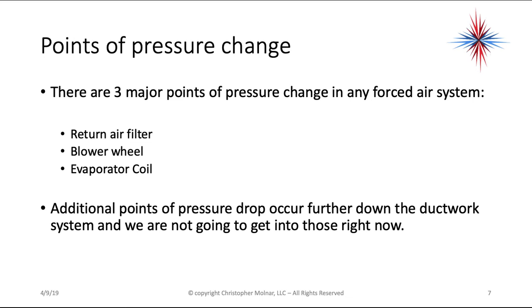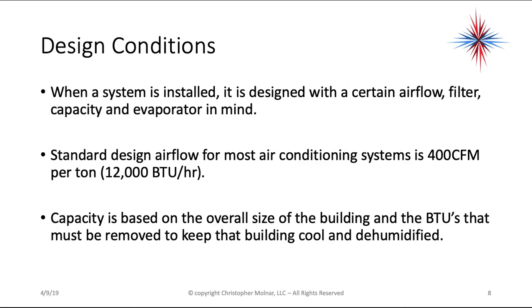There are three major points of pressure change in any forced air system: the return air filter, the blower wheel, and the evaporator coil. Additional points of pressure drop occur further down the ductwork system, and we'll address those separately. When we talk about design conditions, it is when a system is installed, it's designed with a certain airflow, filter capacity, and evaporator in mind.